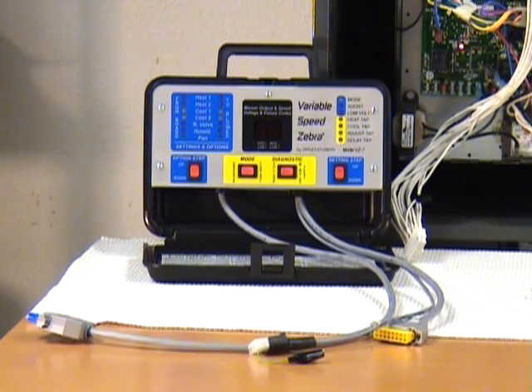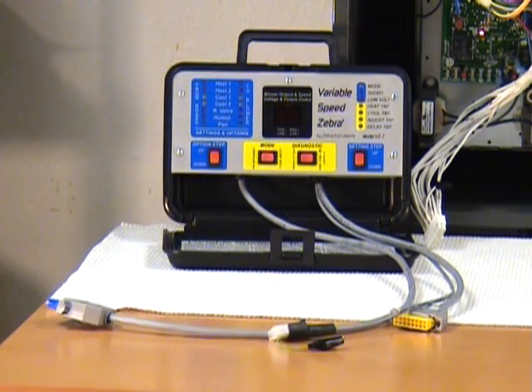Seek competent advice when you're unsure on how to perform a specific job or a function safely. To be safe, give the system and the wires a visual inspection first. If you see melted wiring, for instance, don't connect your variable speed zebra. You might expose it to line voltage and it will stop working. The variable speed zebra is designed only for HVAC blower motors whose control voltages don't exceed 28 volts.